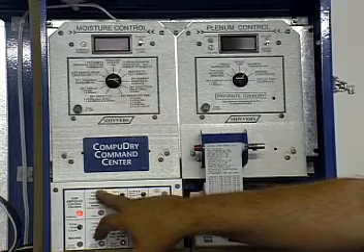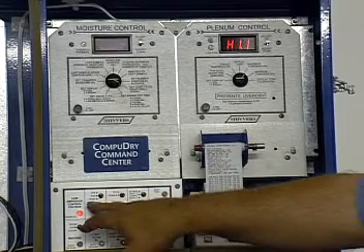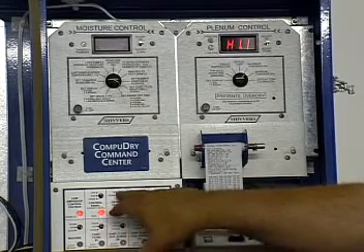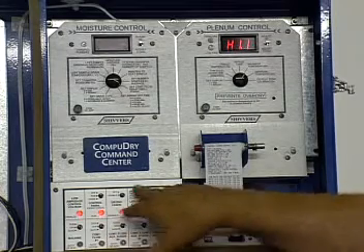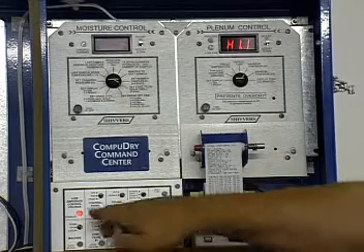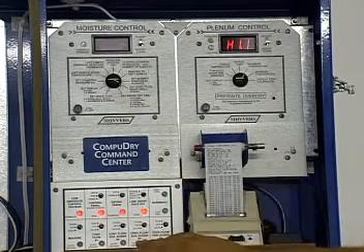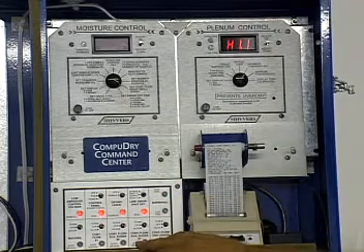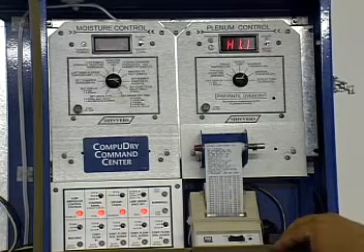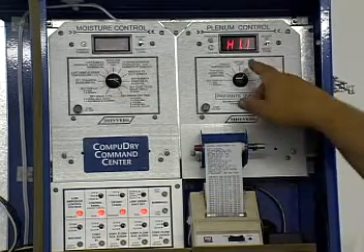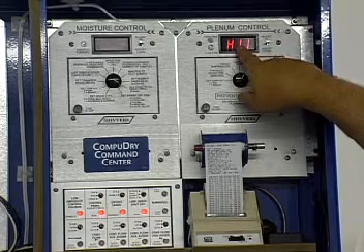Go down here again, we're going to spring load this, start control panel. We're going to go to the fan enable switch so we can physically go back and start the fans. We're going to go up to bypass right here so all our lights are lit. Now you would go back, turn the toggle switch for the fans on, turn the toggle switch for the burner on, make sure the gas valves are open, and this will start and fire the burner.